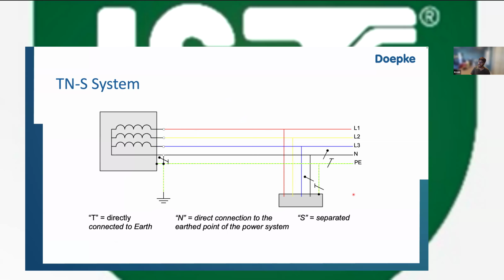So the first thing is that we have a TN system, particularly a TNS system. In a TNS system, the live parts, which is the transformer's windings, the star point, is connected to the general mass of Earth, and the exposed conductive part, which is the body of the equipment, is also directly connected to the Earth point of the power system. So there is a metallic return conductor going from the body of the equipment all the way through the protective conductor back to the transformer star. T means that the source is directly connected, N means that the load or the equipment is also directly connected back to the Earth point, not to the general mass of Earth, the Earth point. And the letter S designates that the live conductor, in this case the neutral conductor, and the protective Earth conductor are kept separate throughout the installation. There are two separate conductors. This is a 5-wire system that we have here.